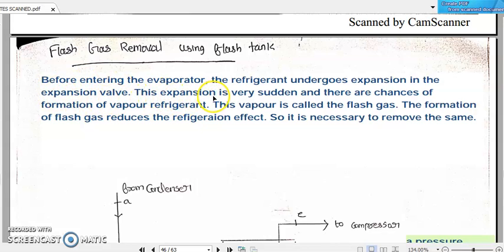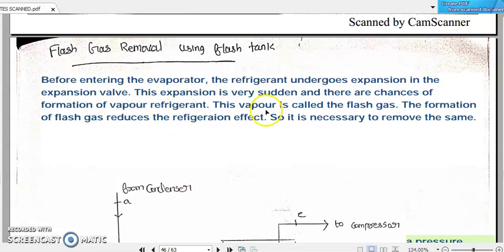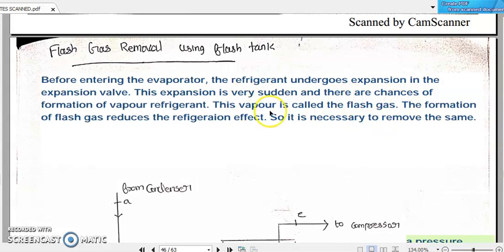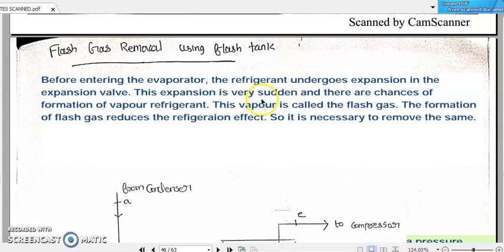During this throttling process, the expansion is very sudden. It happens all of a sudden and there are chances of formation of vapor refrigerant. The refrigerant entering the throttling valve will normally be in liquid state, but due to this sudden expansion, there are chances of vapor refrigerant getting formed. Such vapor getting formed is called flash gas — just like a flash, vapor getting formed due to the sudden expansion inside the throttling valve.